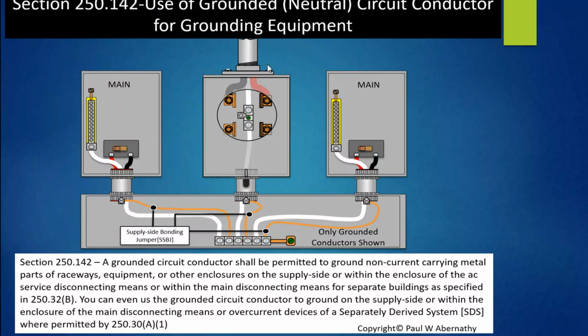So here we've got the raceway coming in. It's connected to this enclosure through a hub. This hub has 4 screws on it. It bolts through a threaded entry that is listed in 250.8. It's all acceptable. It connects to this enclosure. This enclosure is connected to the grounded conductor through this screw here, and I use green here to show that it's made that connection. All right, and that encloses all that. Now, this is all good.